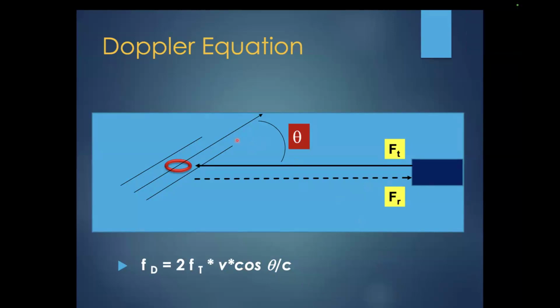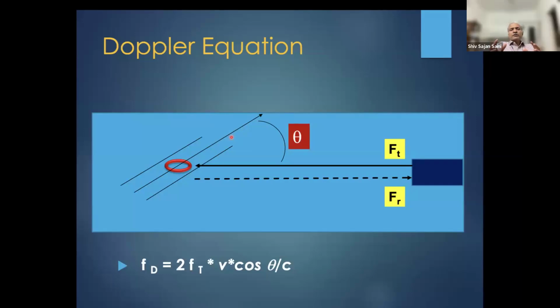So this is important because there has to be a permissible angle up to which we can capture the real velocity, and above which the velocity measurements will be confounded, and that angle is 20 degrees. So we allow only 20 degrees between the line of the beam axis and the line of motion of the object inside the body. If the motion of the blood, or the motion of the tissues inside the body, is at an angle to the beam line of more than 20 degrees, then all the velocities calculated by putting in these formulas are likely to be underreported and false. Okay, so try to align the motion of the object inside the body with the beam line as much as possible, so that our measurements are correct.